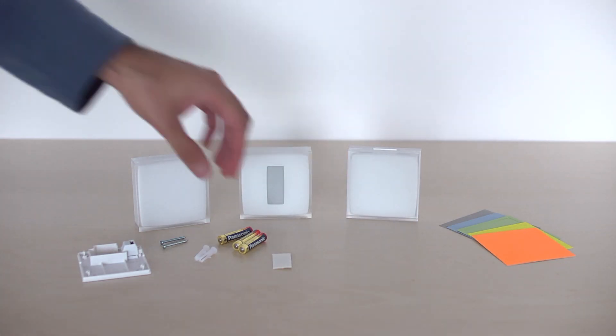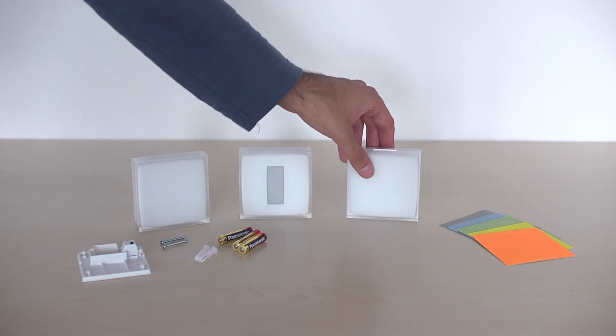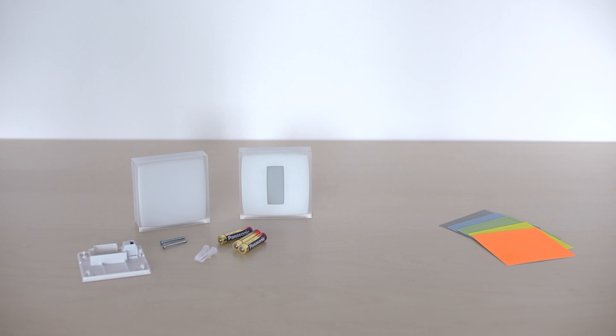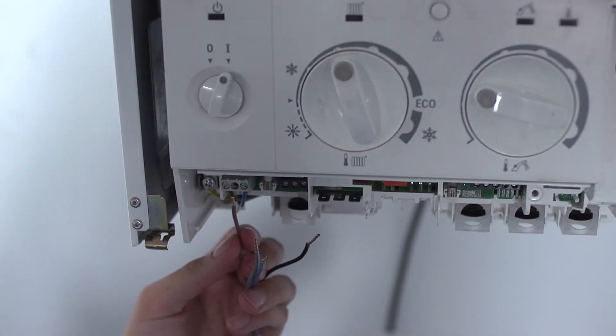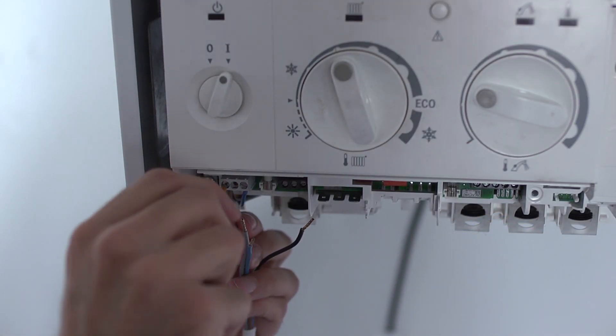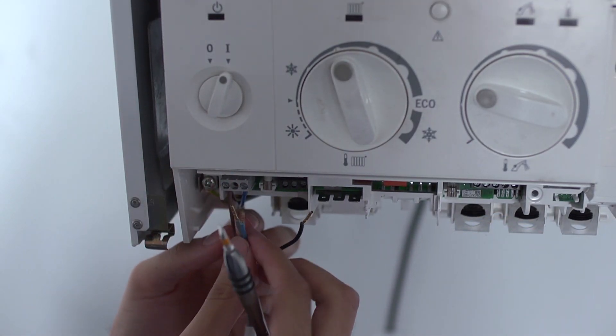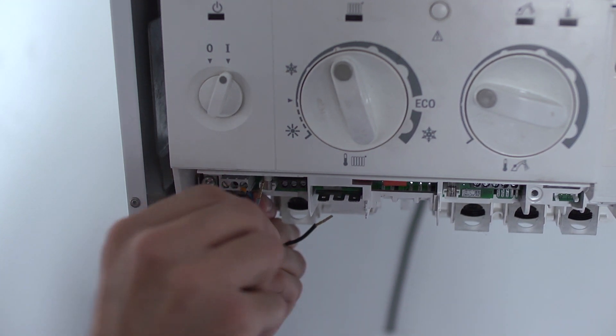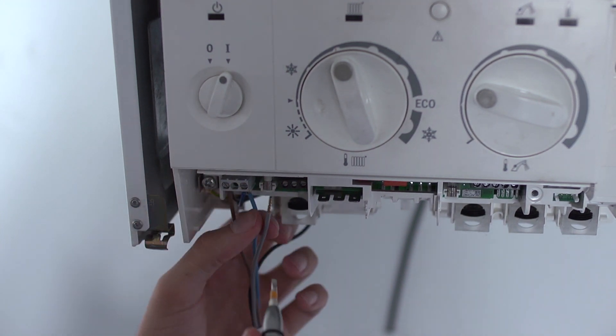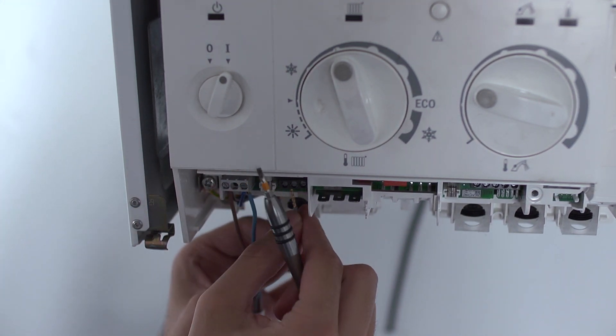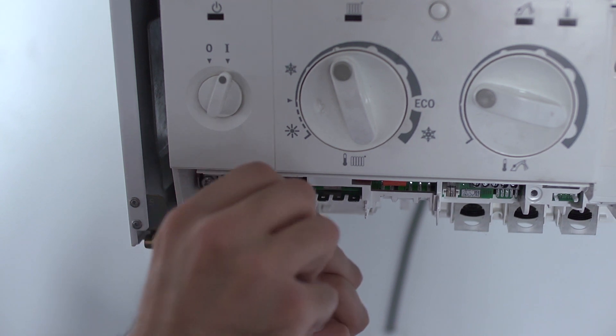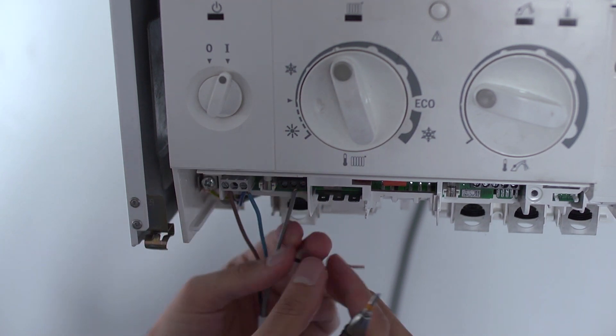Take the relay and the boiler adapter. Plug in the blue and brown wires from the boiler adapter to the power feed terminals previously identified. Plug the black and gray wires from the boiler adapter to the entry terminal of the thermostat previously identified.